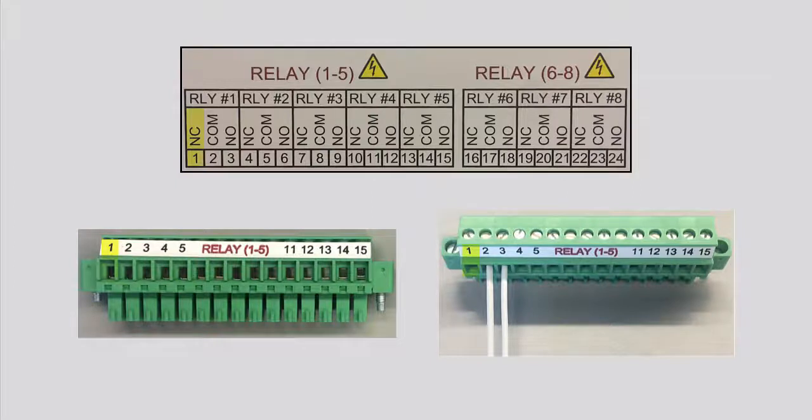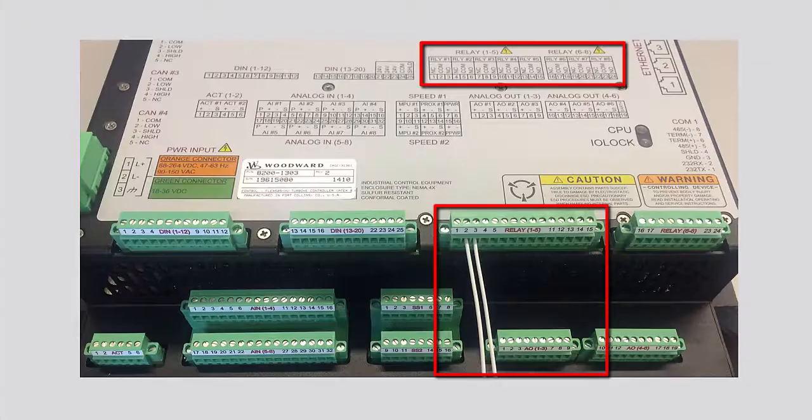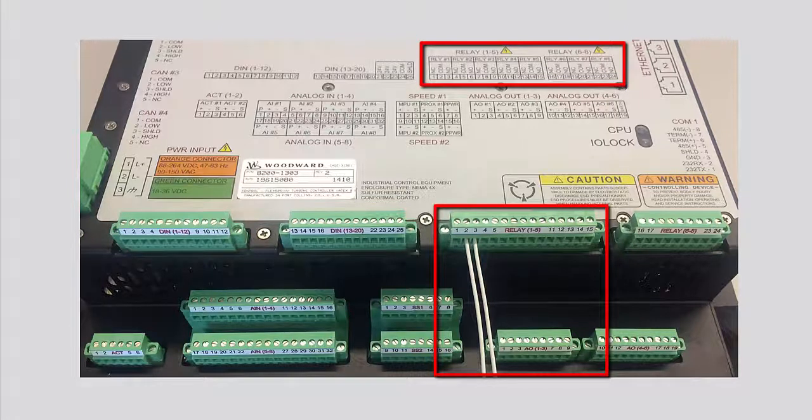Power source voltage should be wired to either the normally open or normally closed contact. In this demonstration we will wire to the normally open contact of relay 1. If relay power is wired to the normally open contact, the end device will be connected to the power source when the relay is turned on or energized.